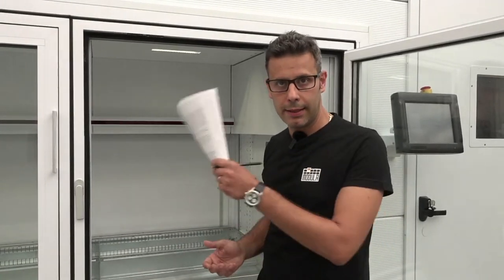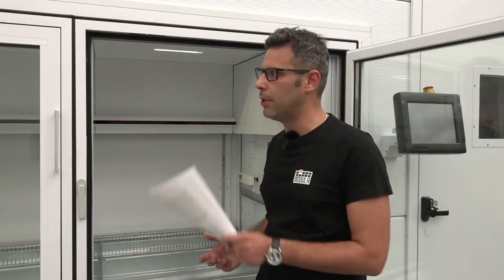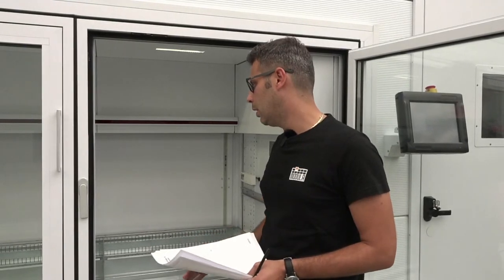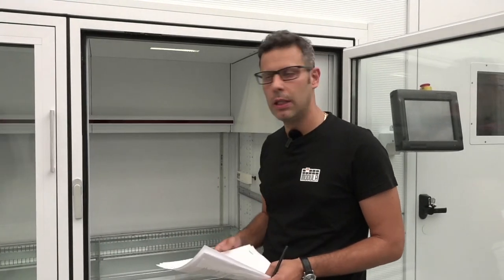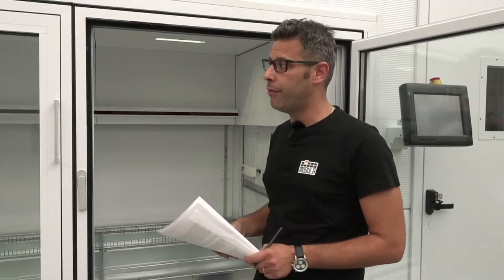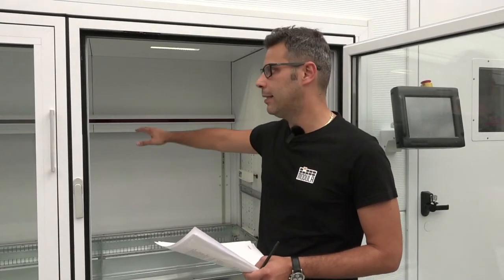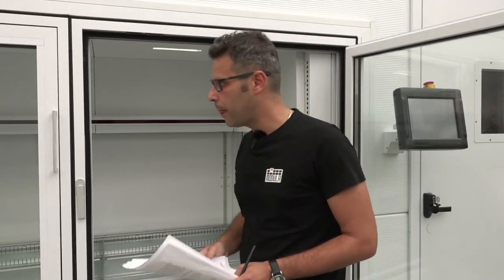It's possible to have a set point of temperature and relative humidity here on the bay, and the machine starts to go into automatic mode only when this temperature is reached. It's very useful to avoid thermal shock in the trays behind this door.